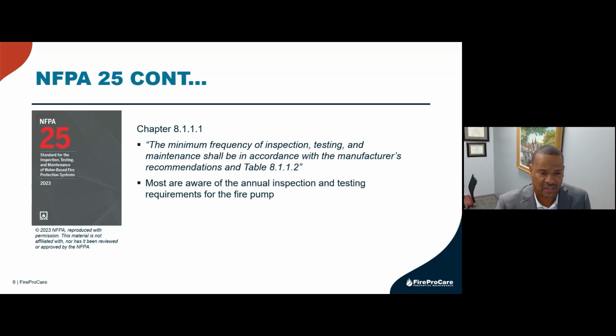No one, since I've been involved in fire pump controllers, has ever come to the manufacturers to say, what is your recommendation when it comes to inspecting, testing, and maintaining your system, your controller? We know how to maintain the system. We know annual tests happen all the time. That's probably the major thing that everyone takes care of, making sure that each year they test their fire pump system and flow water and make sure that the pump is hitting the curve. It meets the design criteria. But for the controller, which is one of the most important pieces of the system, there's nothing there.